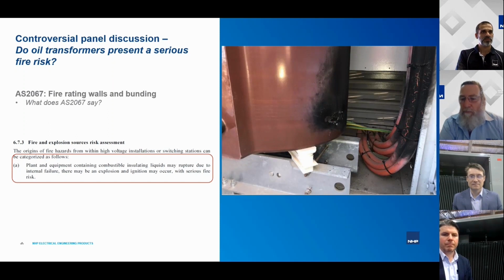Oil transformer, we can kind of think of it more as an exothermic reaction. Now, we talked about the fact that transformers are bulletproof, and I gave the example of one where the oil had got down below the top of the coil and it still hadn't gone bang. Part of the reason for that is that if you just simply think about a fire triangle, we need a source of material to burn, we need heat and we need air. And I think in the example I gave before, the only reason the transformer didn't go bang is because it was sealed and the tank didn't actually rupture. There wasn't actually an arcing event in that particular case. And so therefore the fire didn't start.